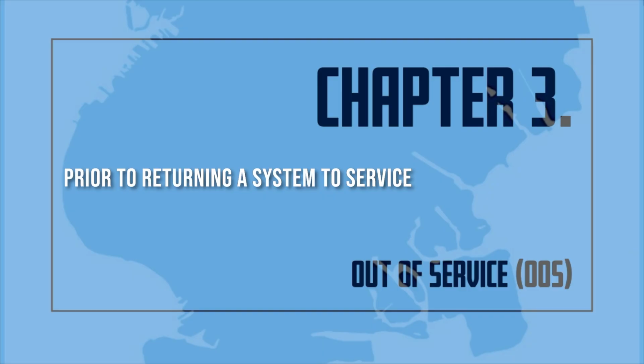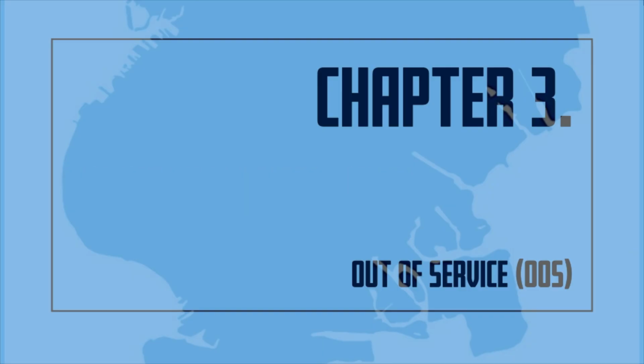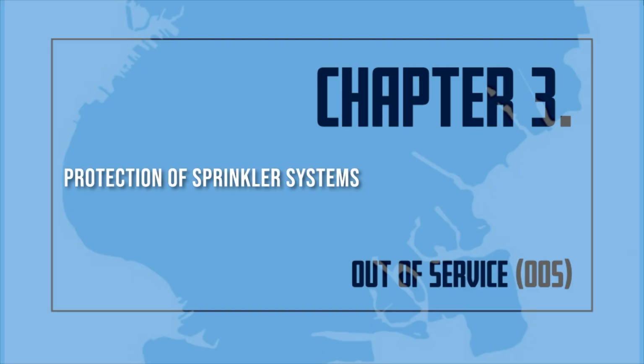Fire Code 901.7.6. Protection of sprinkler systems. All parts of an automatic system exposed to freezing temperatures shall be protected from freezing, or in lieu thereof, an automatic dry pipe system or a system filled with a non-freezing, non-combustible solution shall be used.